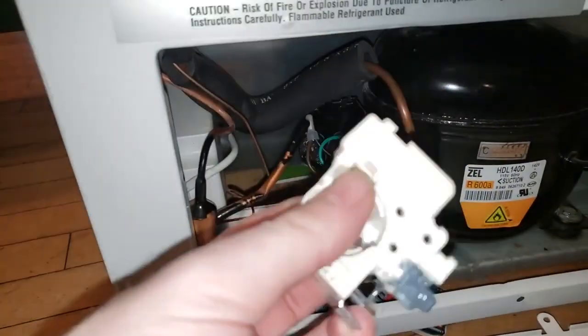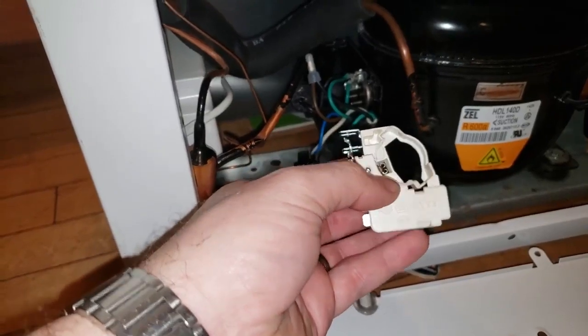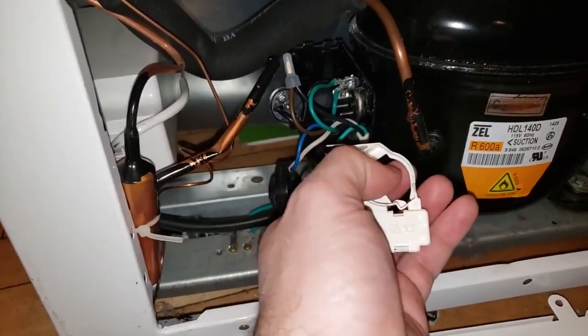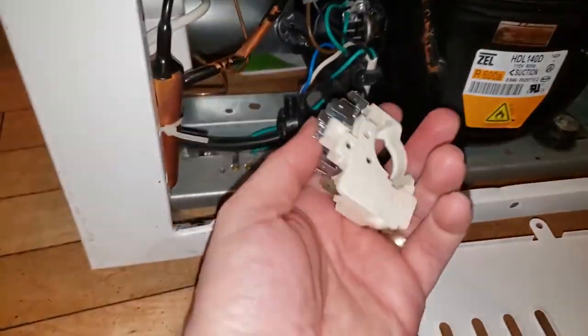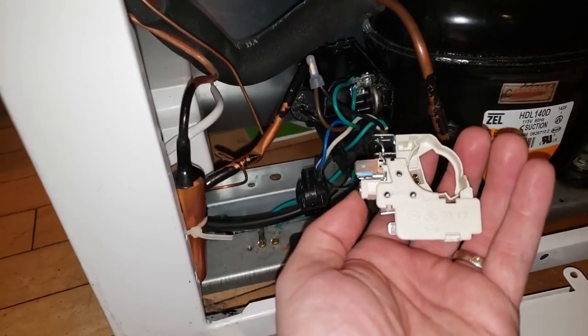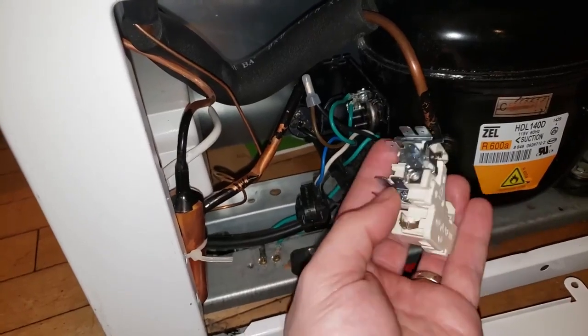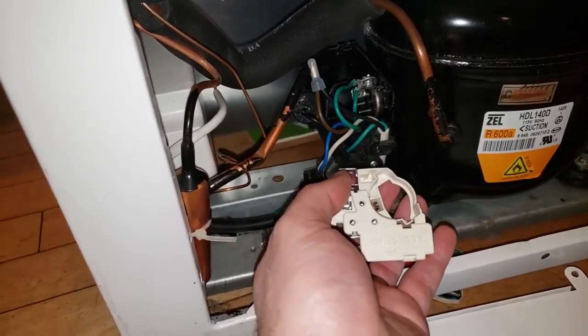Don't worry — the power is unplugged right now. There are two pins here where my fingers are touching, and actually a third one behind the unit. These correspond with the three pins on the original relay, which plugged in just like this. I used a multimeter to trace where these all go: the top one went to the black circle — the overload protection — at the 12 o'clock position, and then the blue and white wires went to one of the other two pins via a connecting bar.